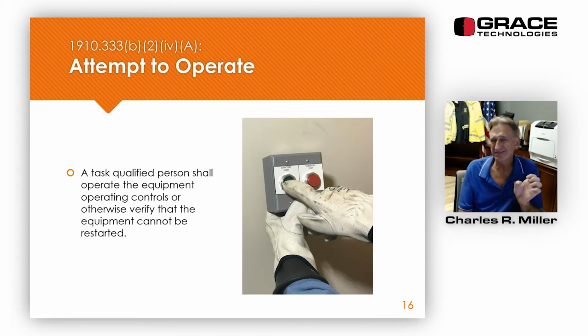Sometimes in industrial plants I've used an electric overhead garage door. Once we shut off the disconnect or turn off the breaker, lock it out, tag it out, then someone will attempt to operate the control to raise or lower the electric garage door. So it's just one additional little step. I like adding this in. It's not in 70E, but what's it going to hurt to try to start the equipment anyway?